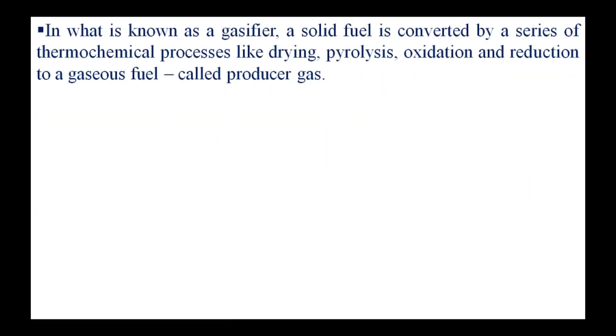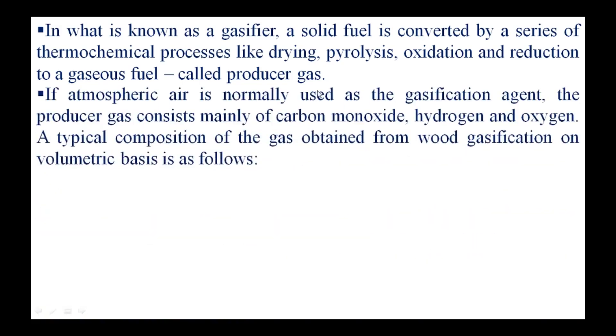In what is known as the gasifier, a solid fuel is converted by a series of thermochemical processes — drying, pyrolysis, oxidation, and reduction — to a gaseous fuel. This is called producer gas. If atmospheric air is normally used as the gasification agent, then the producer gas consists mainly of carbon monoxide, hydrogen, and nitrogen.